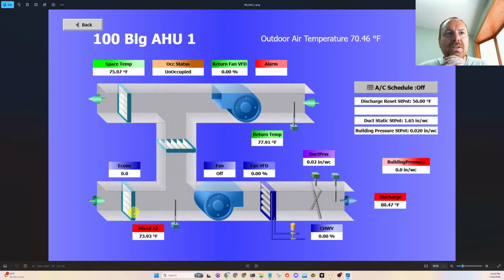There might even be something that could be done on the airflow measuring stations here, where basically if the entire building is direct digital control, we might even be able to do more demand control strategies, even put CO2 sensors in the zones. I should check with some people that are still doing design work, what would be the latest and greatest thing to cut over a VAV system like this. I want to do the duct static pressure reset.